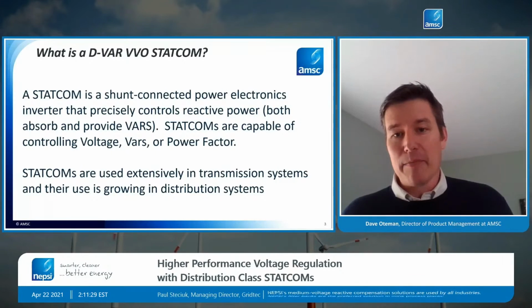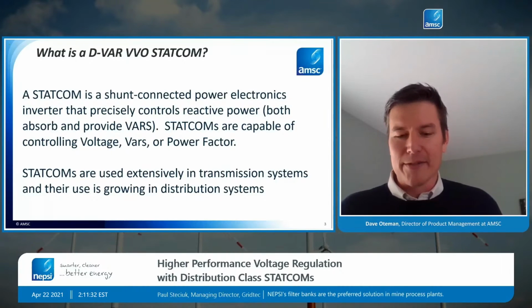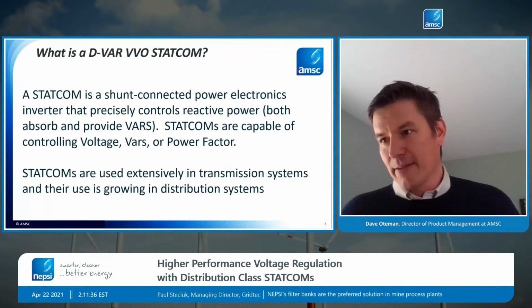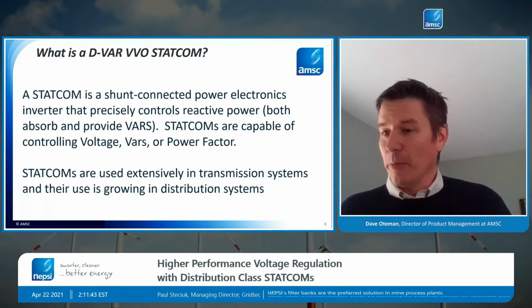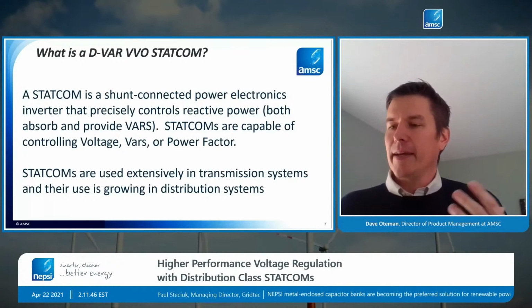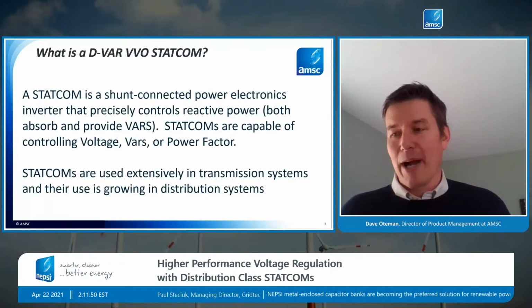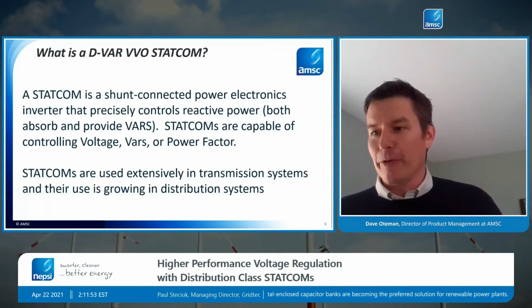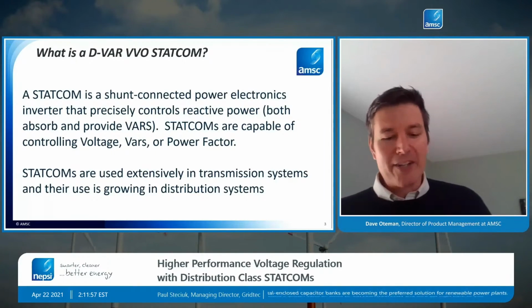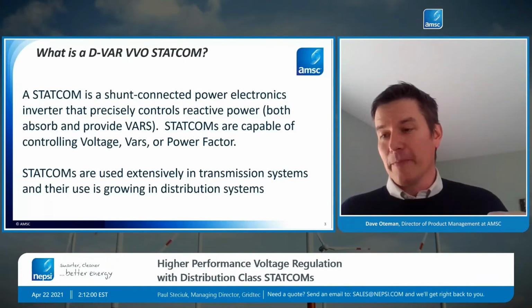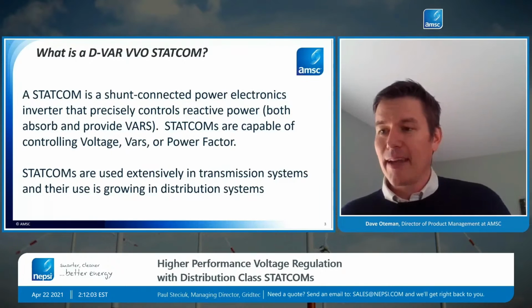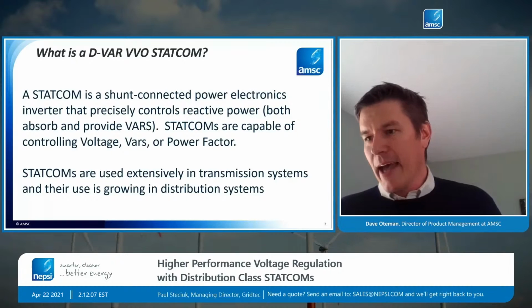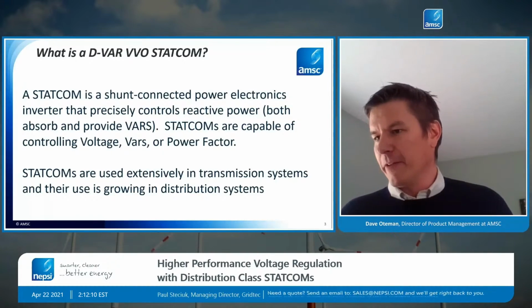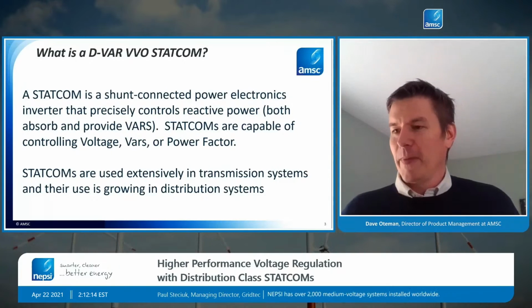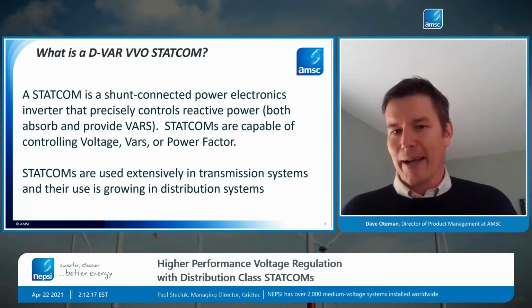A STATCOM is a power electronics inverter that only processes reactive power. Unlike inverters some might be familiar with — a solar inverter, a wind inverter, or a battery inverter — which process real power and maybe a little reactive power, the unique thing about a STATCOM is that it's only capable of processing reactive power. It turns out that, fortunately, because it's only processing reactive power, there are some nice tricks from a technology standpoint that we were able to make in developing our D-VAR VVO STATCOM — specifically tricks to make it very power dense and very compact.